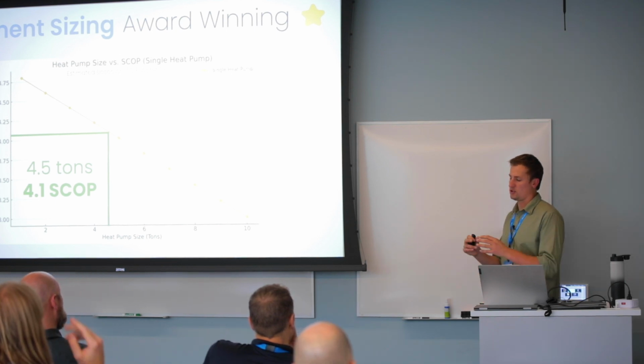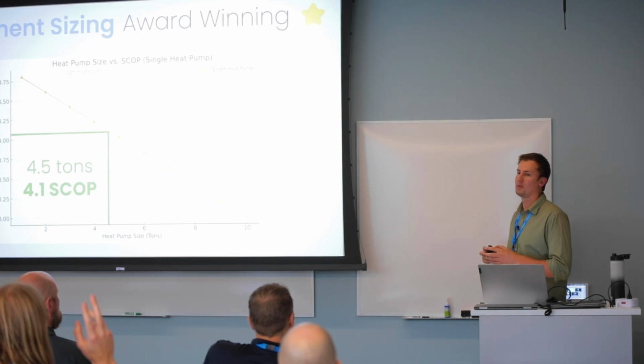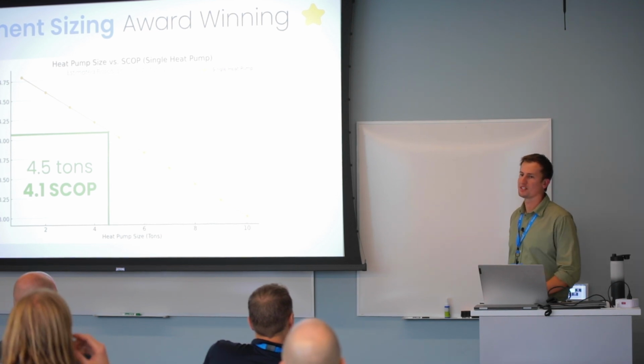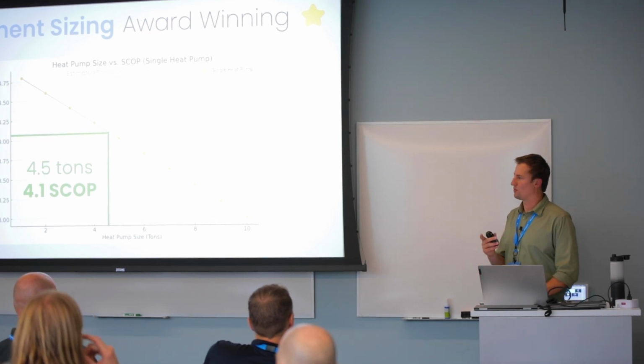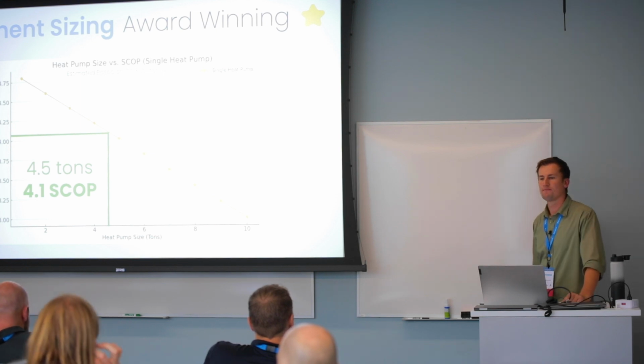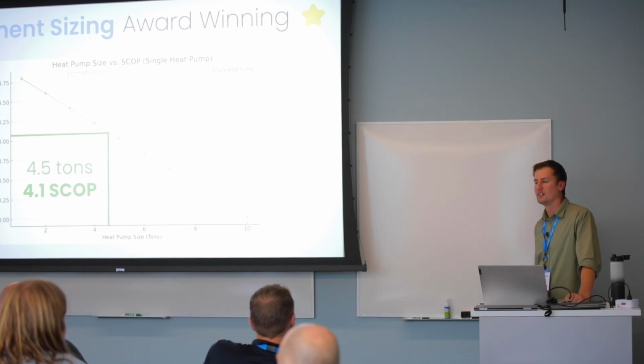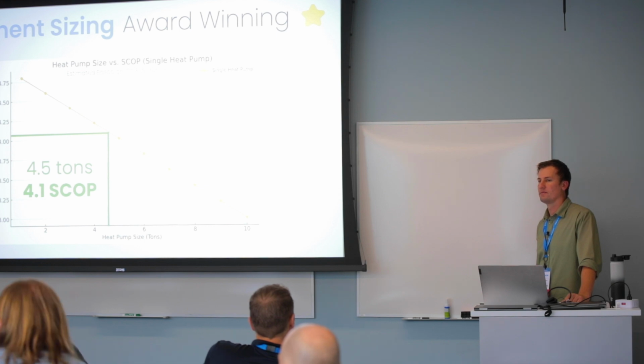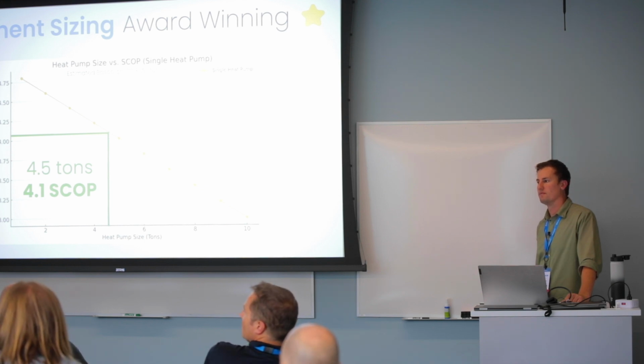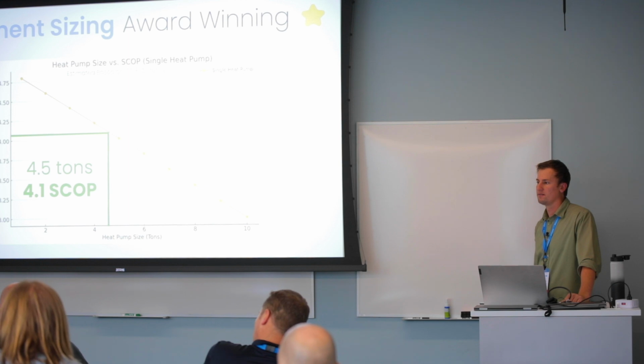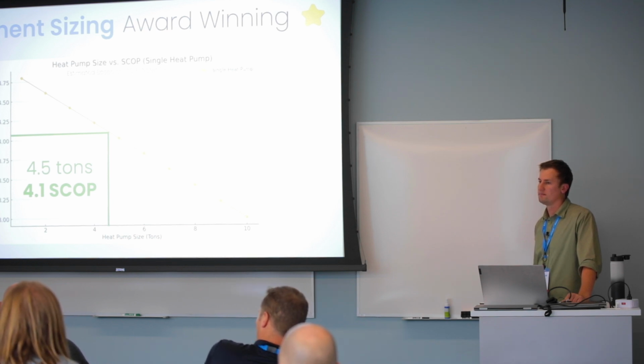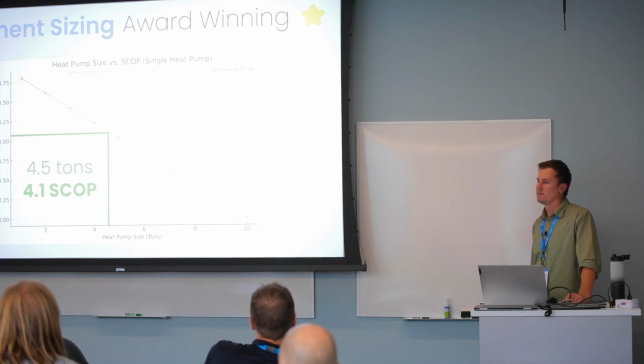You can do it that way, or they can just work together, so essentially combine to 1 pipe, and then it's kind of like 1 system within the building. Yeah, I think it's important to know that's probably most applicable to water source systems. Right, like air source wouldn't probably work that way, I'm guessing. Air to water. Air to water. Air to water, you do that all day long. Yeah. There's cascade, it's lead and lag. Yeah. So we're gonna have the lead this guy's gonna do, and it's based on, it's gonna pull in on the other one to offset that load of the home. Same exact thing, it's modulating turn down ratio on boilers, on hydronic, on high efficiency boilers.